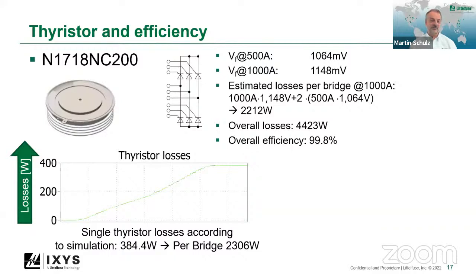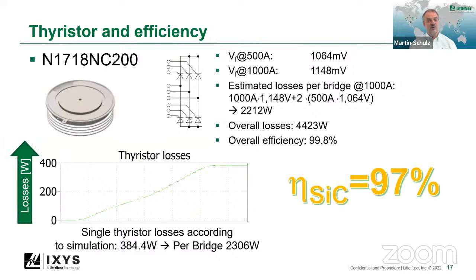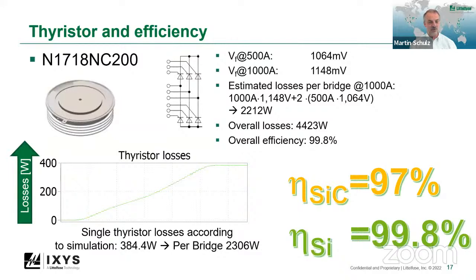So 2,306 watts. As said, silicon carbide solutions have been reported to achieve 97%, potentially 98% efficiency, and that's because you have at least a two-stage energy conversion if you don't have insulation. With an insulated version, there's three stages of conversion, and each stage is burdened with losses. Single stage energy conversion can achieve 99.8% efficiency.